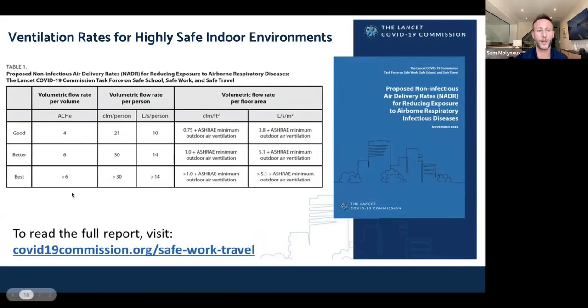For the volumetric flow rate per volume for a space, they've said good, better, best is 4 ACH, 6 ACH, or 6+. You can see how this translates into volumetric flow rate per person and per floor area. If you measure one of these things, and have a couple other variables like floor area or number of people, it's trivial to translate one metric into all of these metrics.